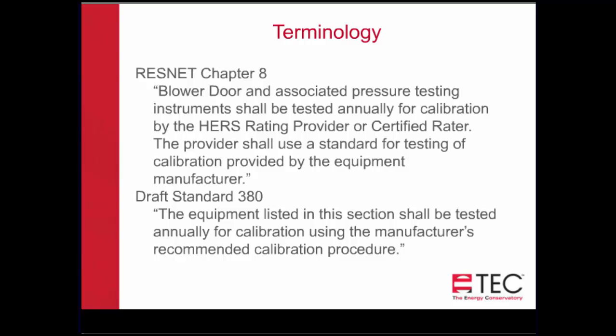In Standard 380, the phrasing is: the equipment listed in the section shall be tested annually for calibration using the manufacturer's recommended calibration procedure. So we were recently asked about this. Our calibration recommendation is for every 2 years to be done at TEC. But we do provide a calibration check procedure, and that can be done annually. And that's what that's referring to.